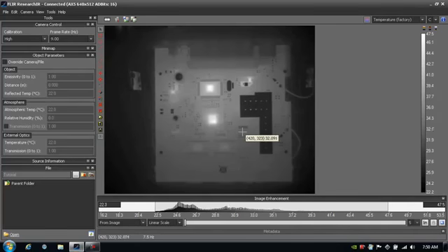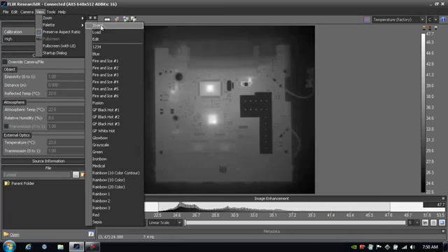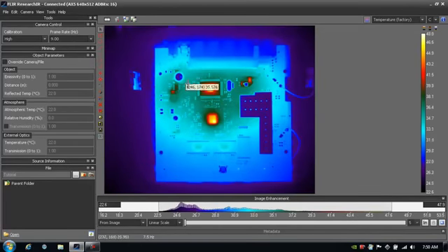Let's go ahead and do some image enhancement to make the image look a little bit better. We'll go to View, Palette, and I can choose from any number of color palettes to apply. I personally kind of like this 1, 2, 3, 4 palette, so I'll click on that. We can see the hotspots on the board and probe around and measure some temperatures. Well, let's say that I'm only interested in the temperatures on the board and not here in the background.